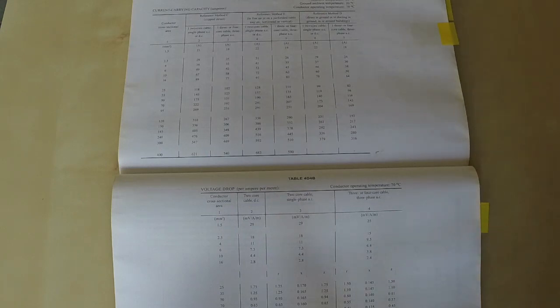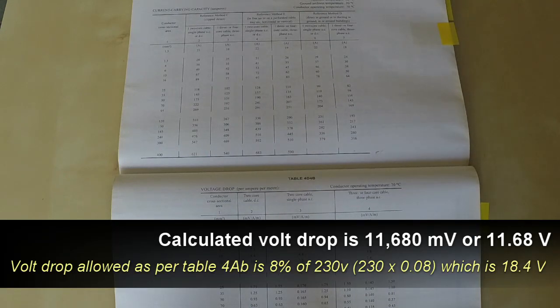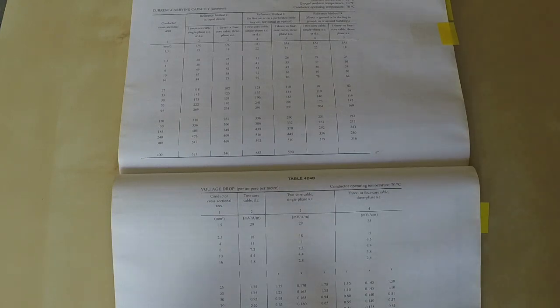If you go back to page 338, the volt drop allowed at 230 volts for all other uses other than lights is 8%, which is 18.4 volts. You can see our 11.68 volt drop is within the parameter of 18.4, so that is okay.